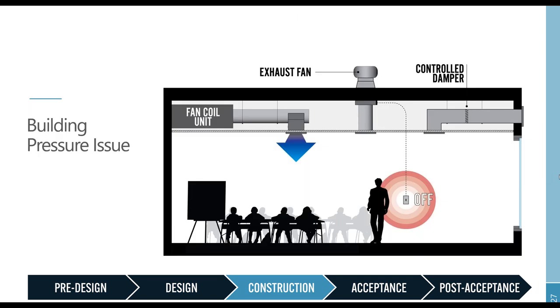So our next example here is going a little bit deeper into the weeds. And this is really an example of how, in my mind, sometimes commissioning can be a mystery. It's an investigation. It's going through and trying to find the root cause of where a problem or an issue comes from. This specific example is from a middle school in Hawaii. And we were in the middle of the commissioning process, and we had, in this case, a science classroom that just wasn't working quite right. We didn't quite know what the issue was, but we could tell that something wasn't working right.